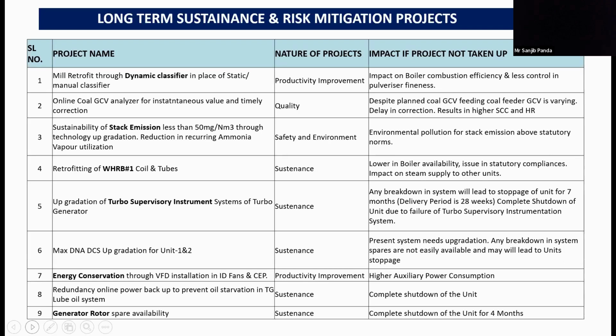Upgradation of TSI systems, and in the same way, next we have Max DNA DCS upgradation. These two are again based on the need of going for new technological upgradation and also to ward off the aging effect. Then energy conservation through VFD installation in ID fans, and this is basically an energy conservation measure. Then redundancy online power back to prevent oil starvation in TG lube oil system. Generator rotor spare availability. Right now we have 2 units which are always in operation, so we do not have a spare unit where in case of any need of replacement of spare, or maybe to refurbish any of the spare, there is no, we are thinking of going for a generator rotor spare.